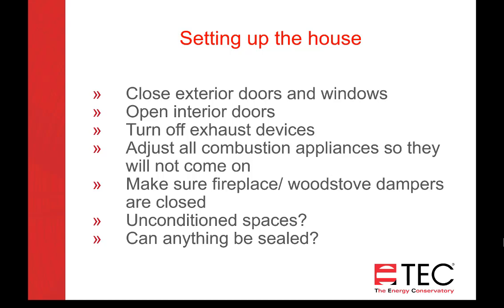Can anything be sealed? The ResNet standard, or the standard that's outlined for code compliance, says the only thing that can be sealed is a continuously operating ventilation system. You can turn that off and seal it on the outside. Anything else you shouldn't be sealing. For example, maybe they have a window air conditioner in there, and if you're doing a test before and after construction and one person seals it and another one doesn't, then you're not getting the same results. So make sure that you have some protocols that you're following to make sure that these tests are repeatable.